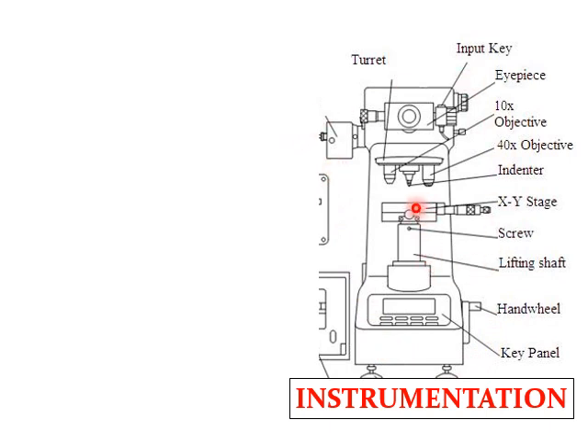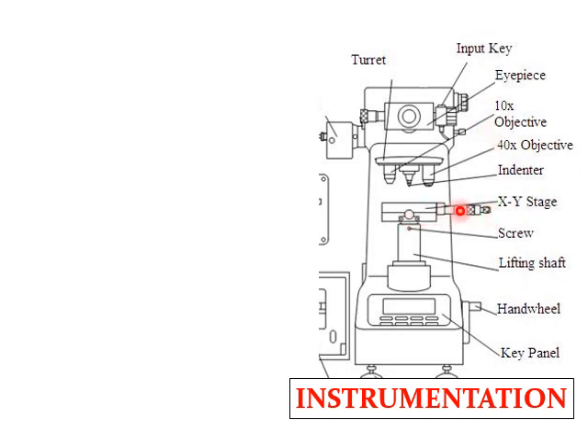A load is placed from the top surface. The testing sample is placed on the anvil with the help of a lifting shaft and handwheel. A diamond square-based pyramid indenter is placed and comes in contact with the testing sample. After an impression is formed, the diagonal length is measured with the help of an optical microscope, which is provided with two objective lenses — 10x and 40x. Both the x and y directions can be measured with the help of an x-y stage.